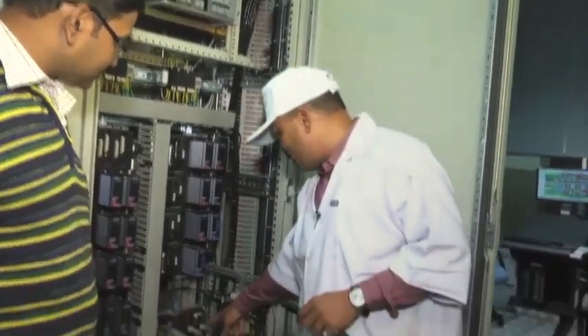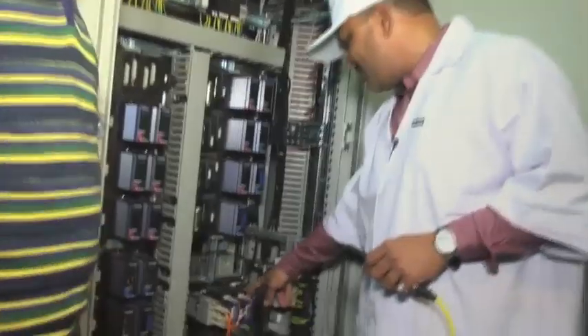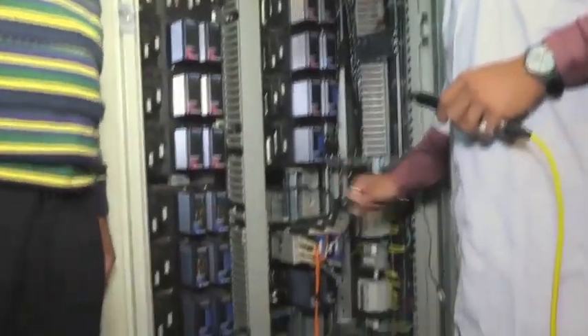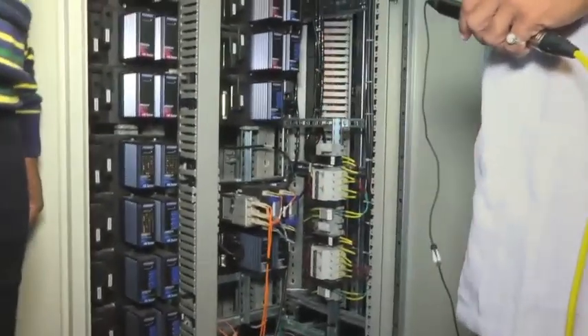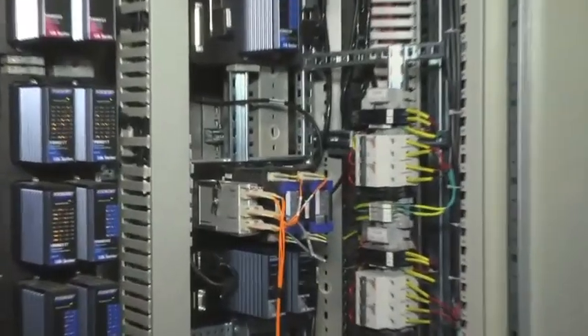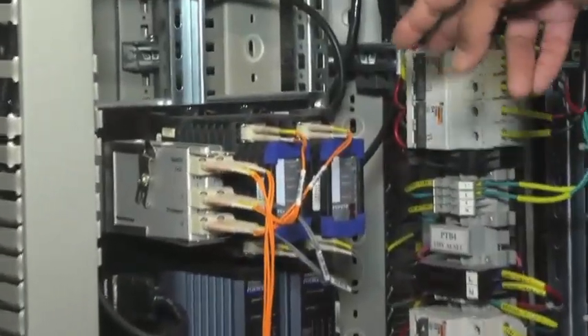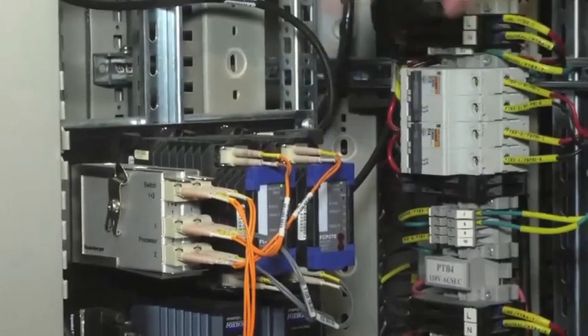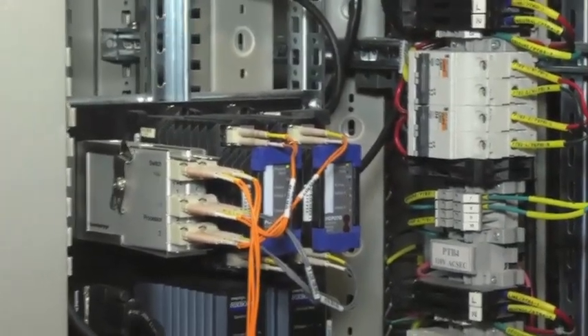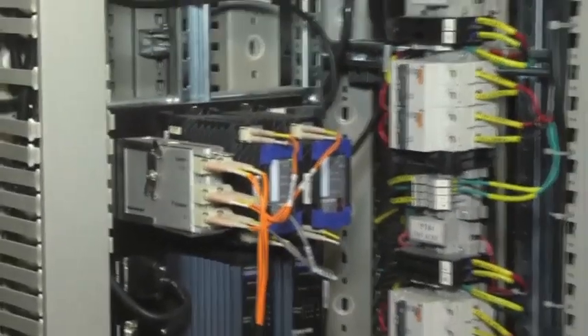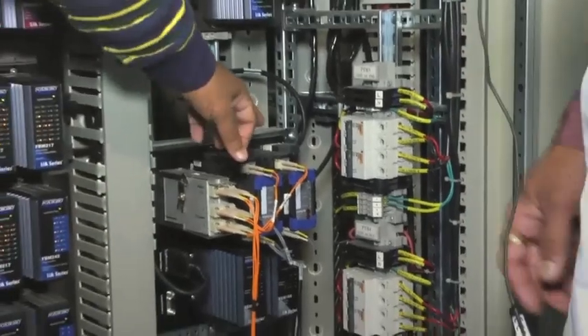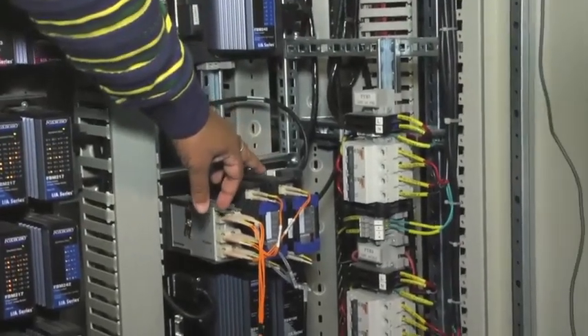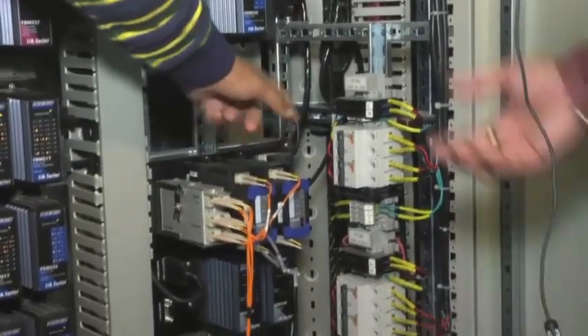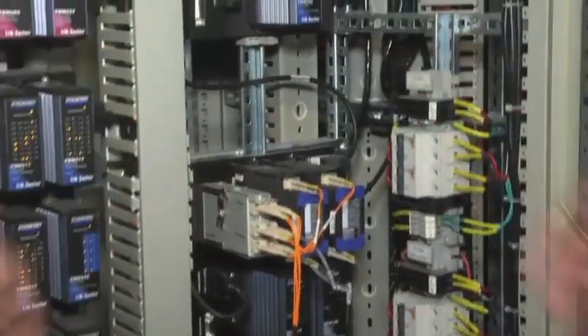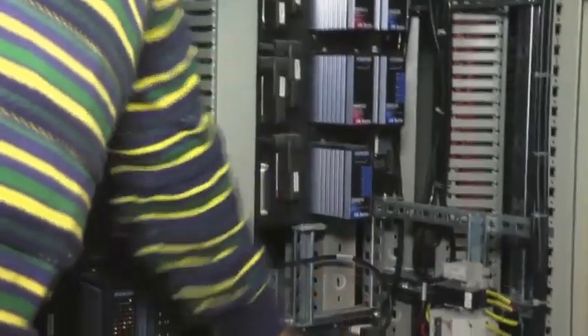Here we can see the two control processors. One question is, why are two control processors installed here? In case one control processor fails, the other one takes over all the controls automatically. So this is basically fault tolerance. If one of these fails, the other processor will take over. The transition is going to happen automatically.